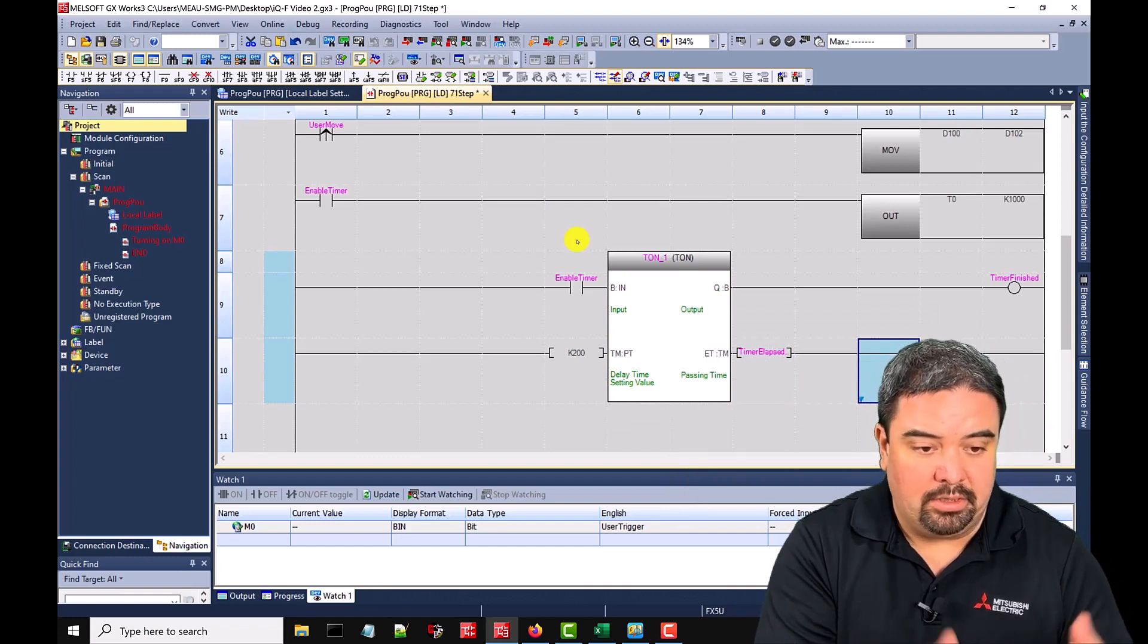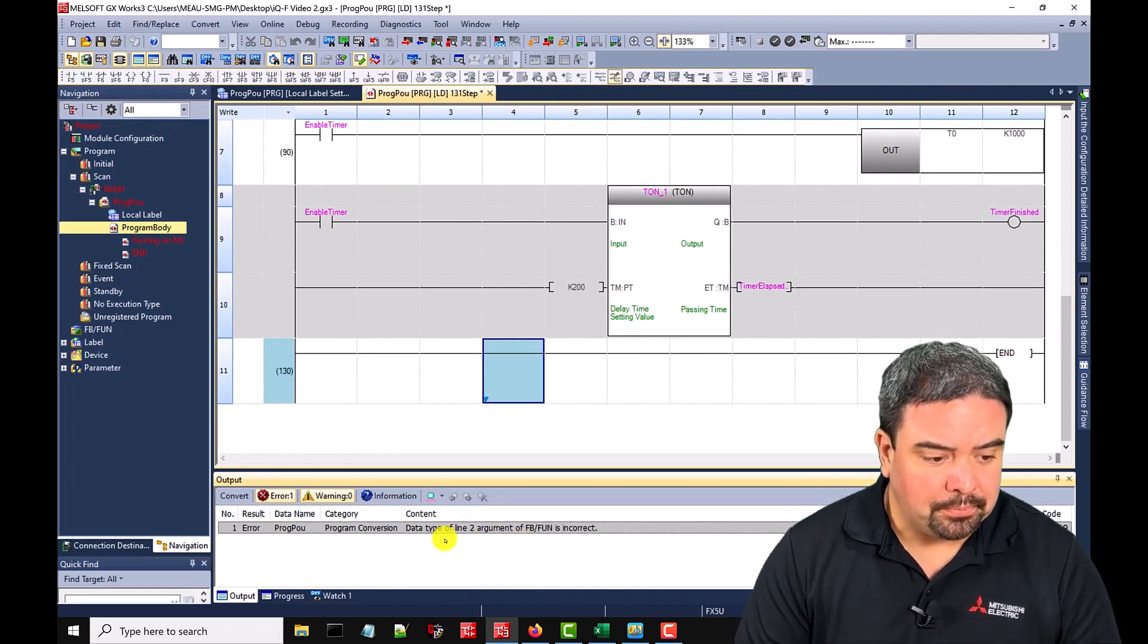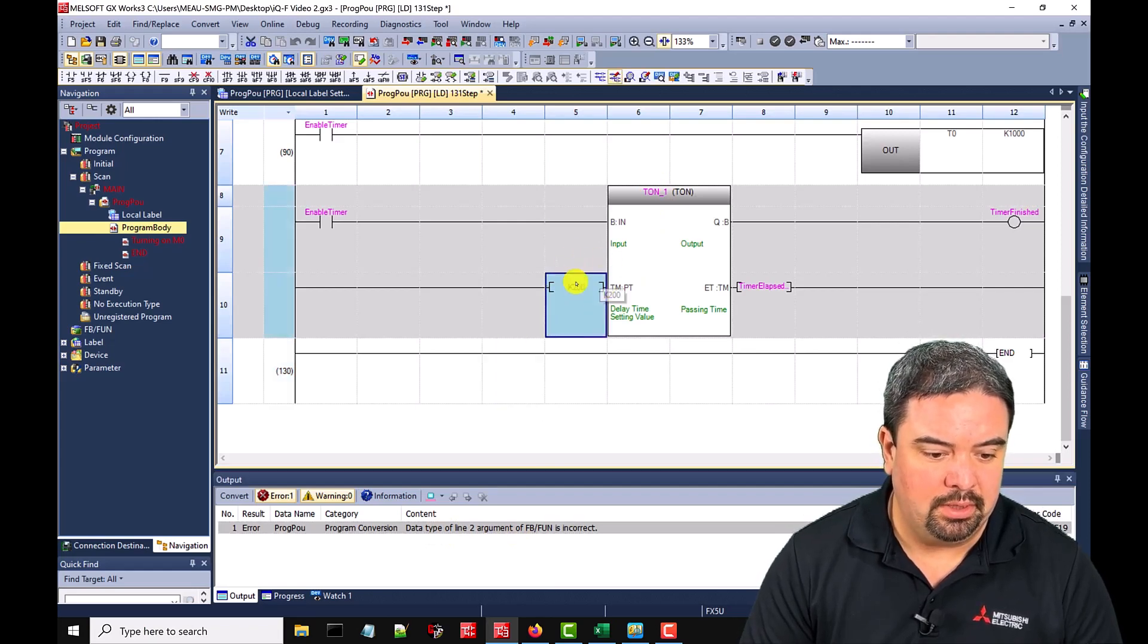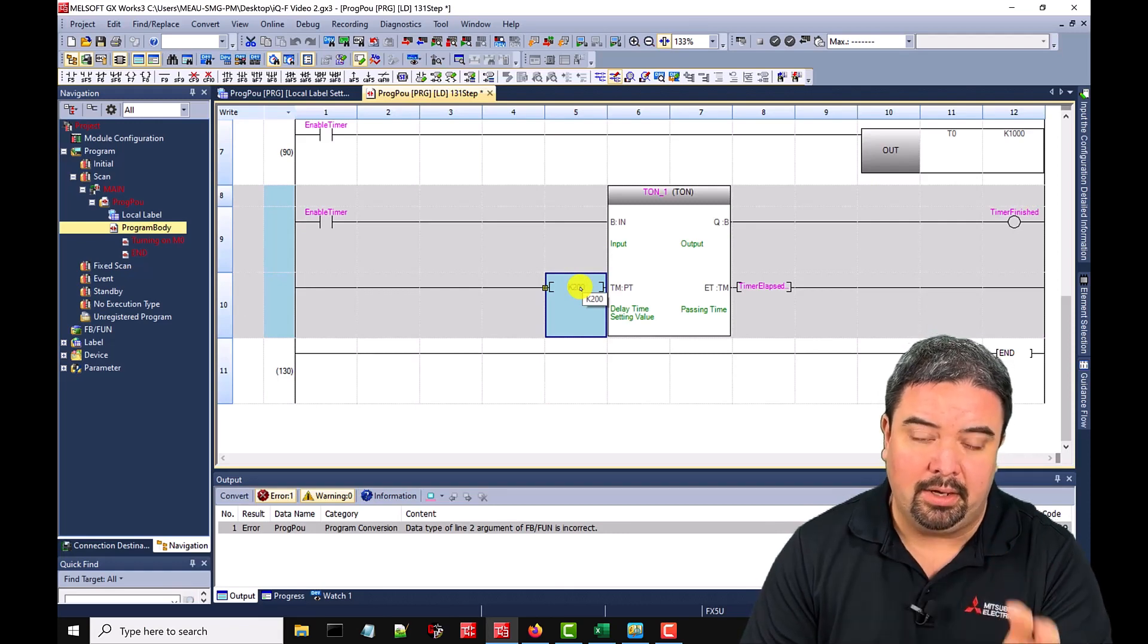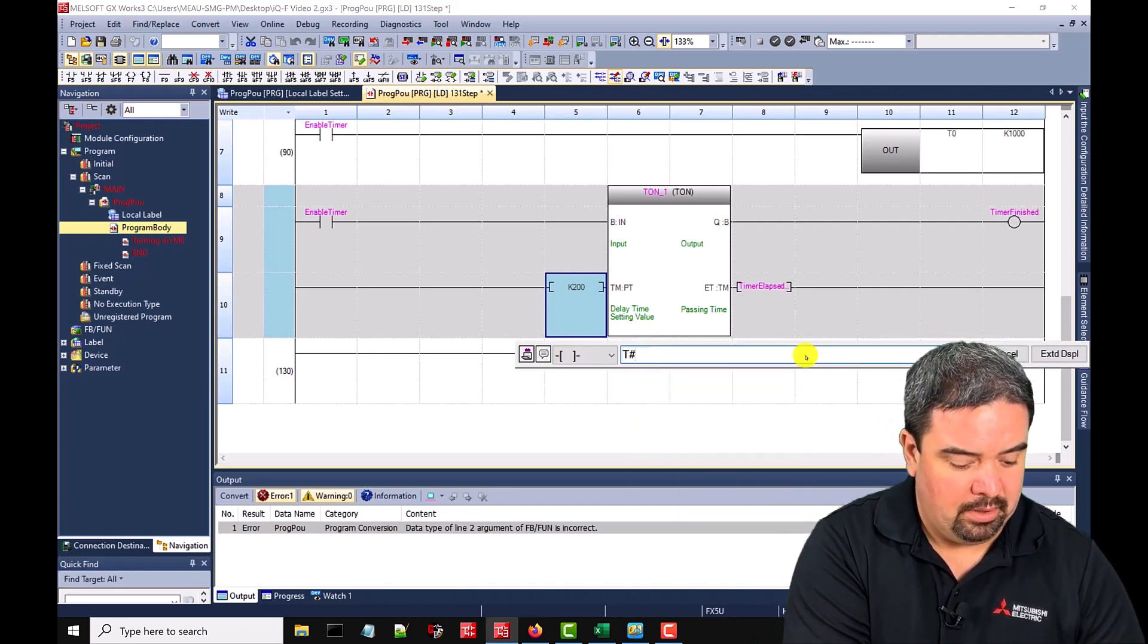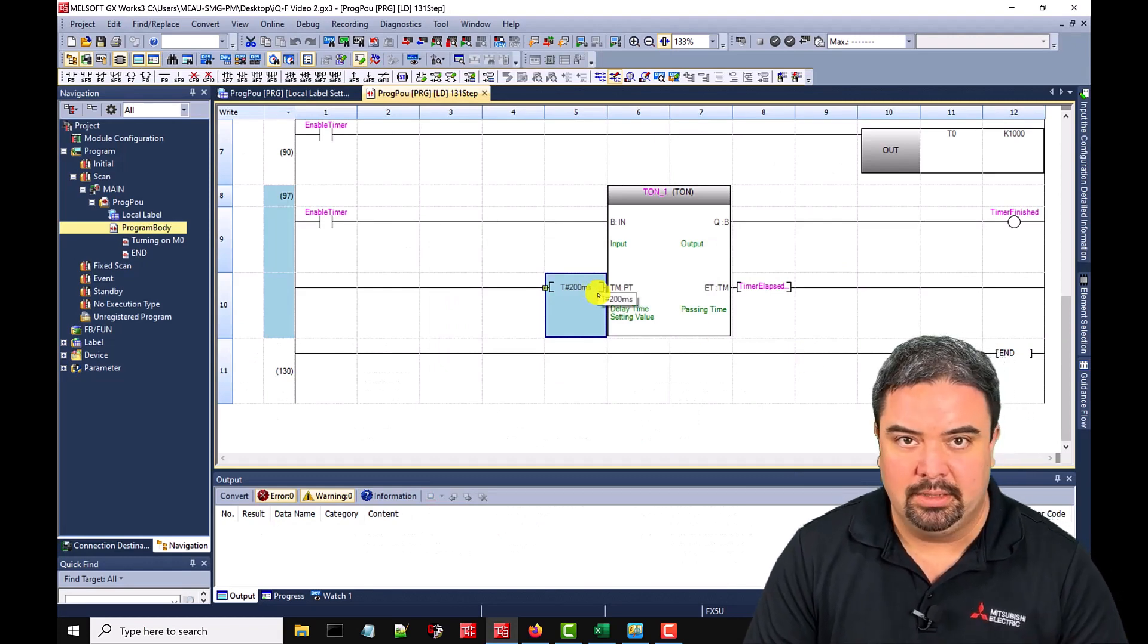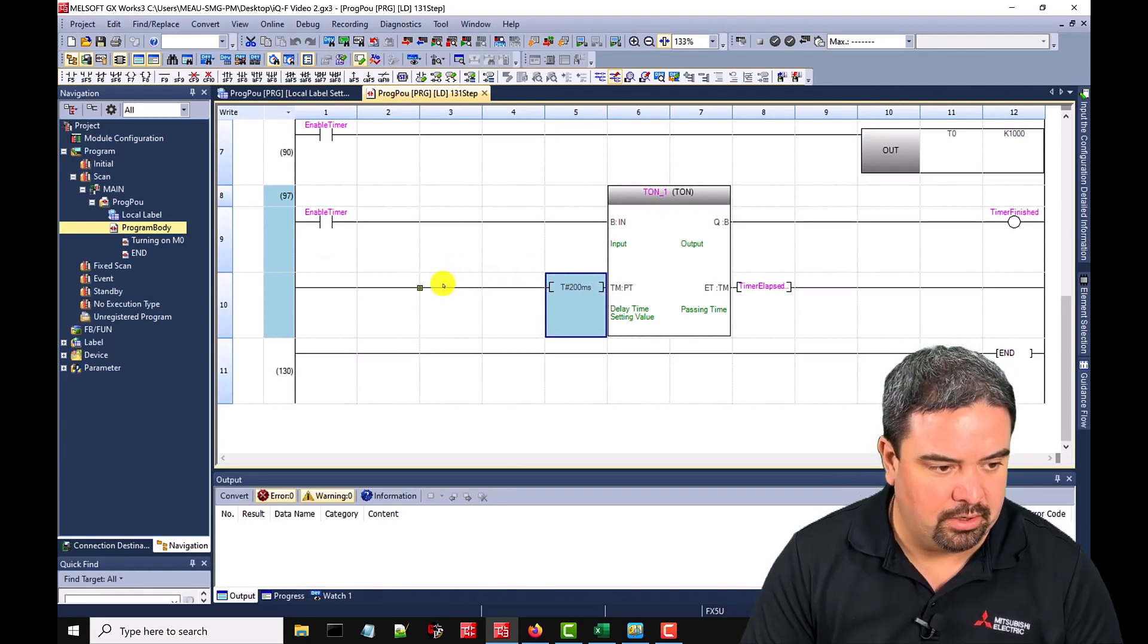Now to compile all of this, I can hit F4. So what you'll see here is after the compile, we have a data type of line two argument inside the function block. So that's line two would be here, the K 200. We cannot use the same K constant in this timing block. It actually wants a time value. So if we just change this to time 200 milliseconds hit F4. Now everything's happy. So we could have said 200 milliseconds, one second, we can give it a specific time. Some people prefer the TON instruction.